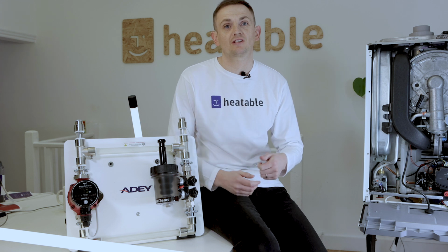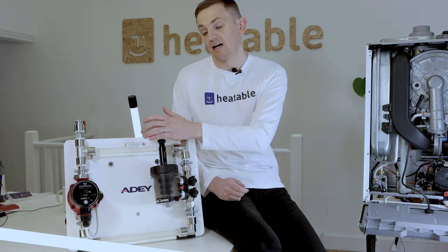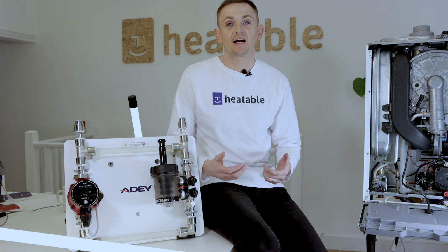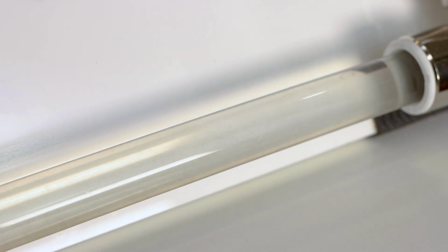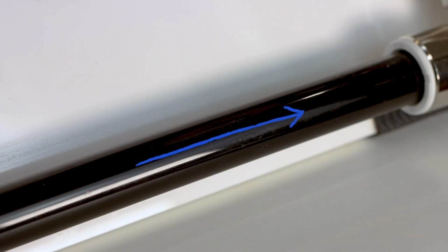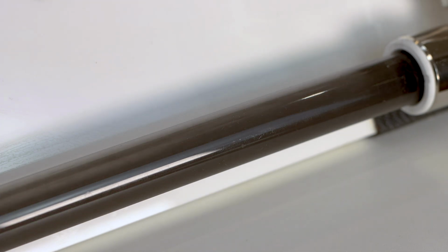So magnetite is essentially sludge, and it's caused from radiators eroding over time because they have water in them. That breaks down the radiator, and those particles are then carried around the system. As the product is metal, it's magnetic, so the job of the filter is to capture the magnetite.